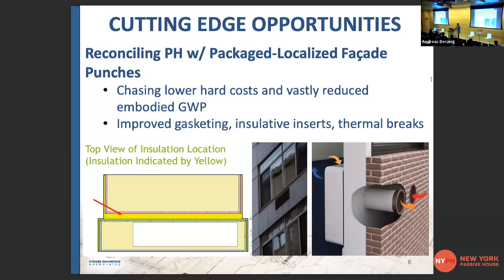The picture on the opposite side is more about what the traditional PTAC manufacturers are doing to turn the system into a mini split. They're actually splitting the equipment by about 8 inches and putting a highly insulative, R6-style spray foam insulation in between the indoor and outdoor sections, where we can turn the PTAC punch in the middle from R0.5 up to R10, R12, R18 values that start to reconcile with the tight envelope performance and energy performance we want for the building. Hopefully that gives you one thought process about how we can break our minds into heading towards packaged systems while also bottling up our envelope.